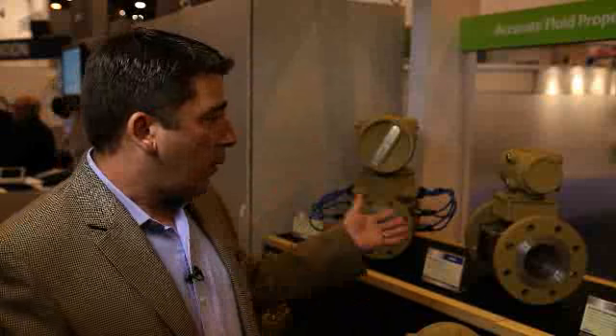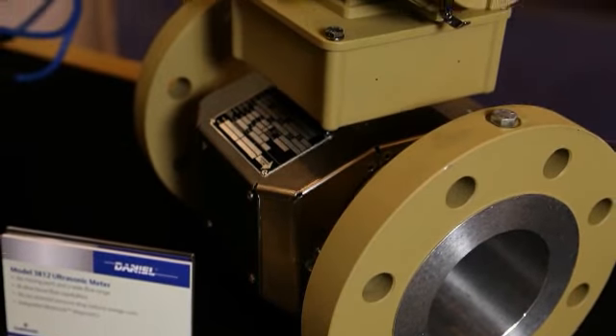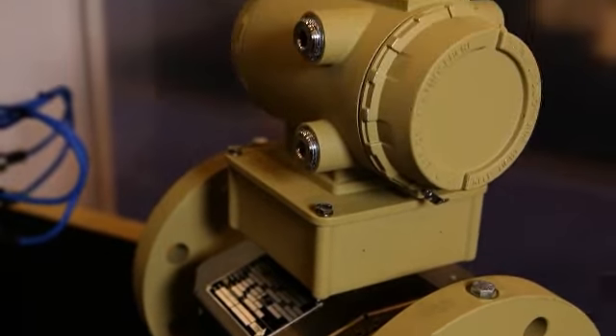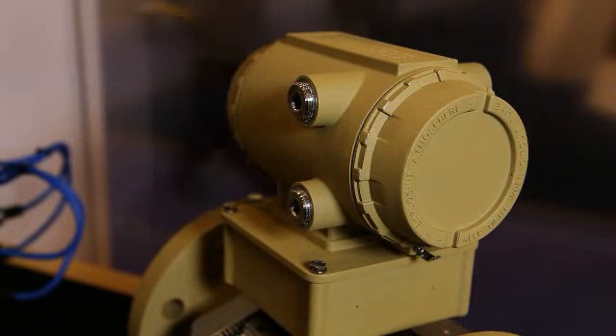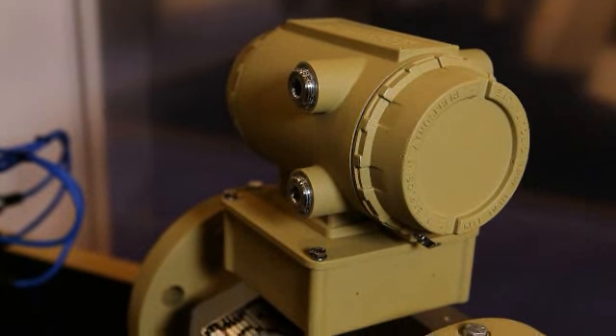Okay, so first I'd like to explain to you how the ultrasonic meter can give you high capacity and increased rangeability when compared with traditional technologies. For example, the ultrasonic meter, as you can see, is a very simple device. We have the meter body here, we have our electronics here, and we have transducers which are located under this housing here. The 3812 is a two-path device. Two paths meaning there are two locations in the flow where we are measuring the flow rate of the liquid.